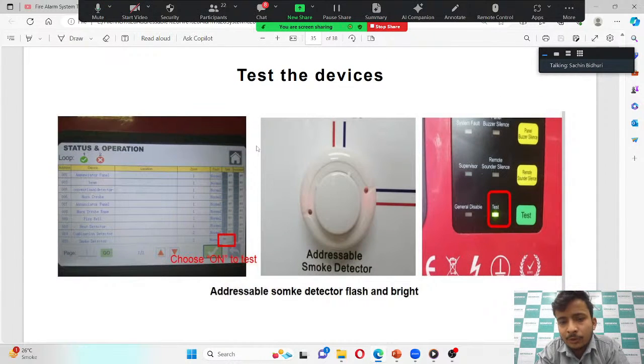Test the device, how will this test of the device work? If you enable the test in the status and operation option, the devices will flash their LEDs continuously. The LEDs of the devices will start flashing, and on the panel also the test LED will glow. So by that you get an acknowledgement that this device is working properly.